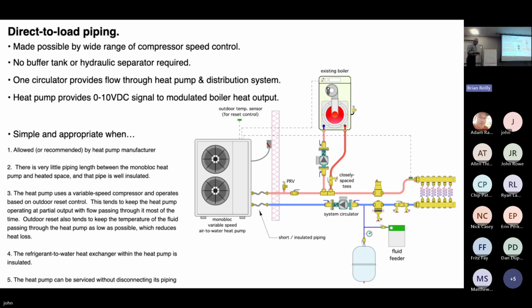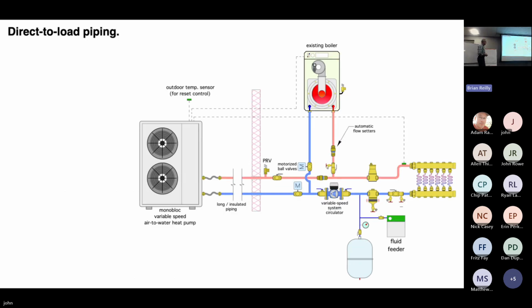Now, if you're going to move the heat pump a distance away, I did a different schematic for it. What I'm doing now is putting a couple of motorized valves in. What would happen is, if the heat pump is out of service, this valve would close, this valve would be open, and the flow is just doing this. If the heat pump is running, this valve would open. That, I feel, is more appropriate when the heat pump's going to be a fair distance away from the building, because again, we don't want to lose a lot of heat outside.